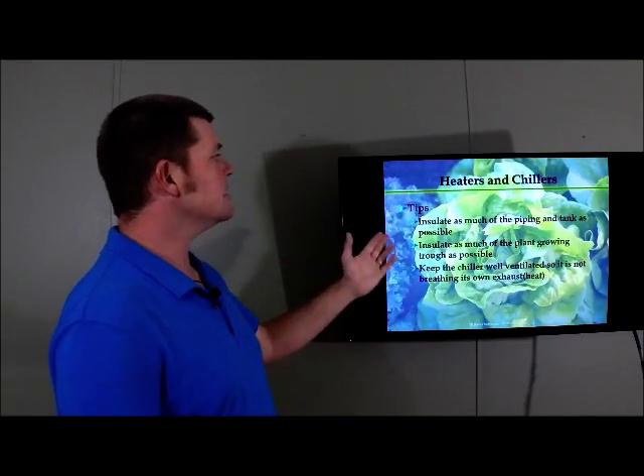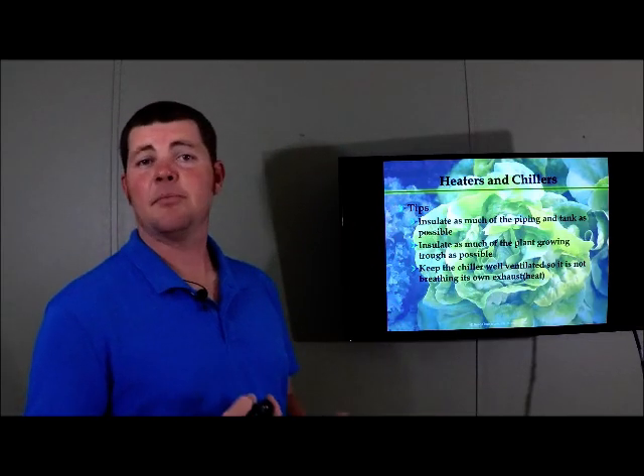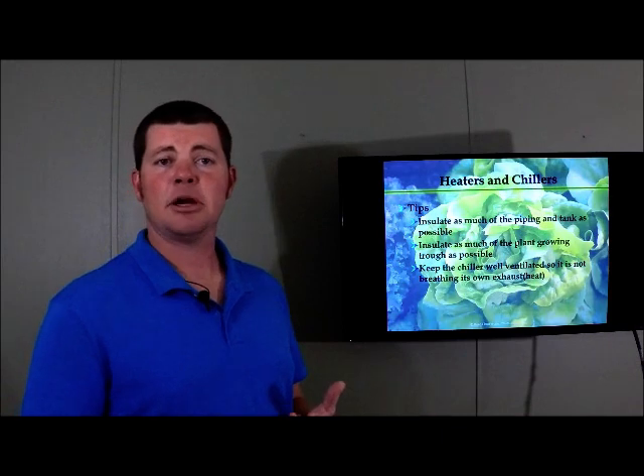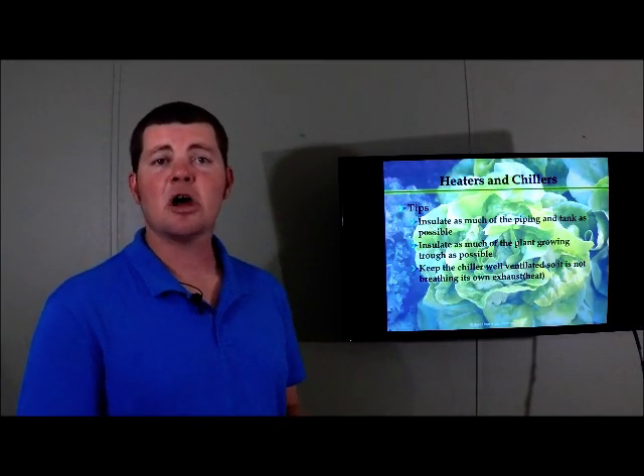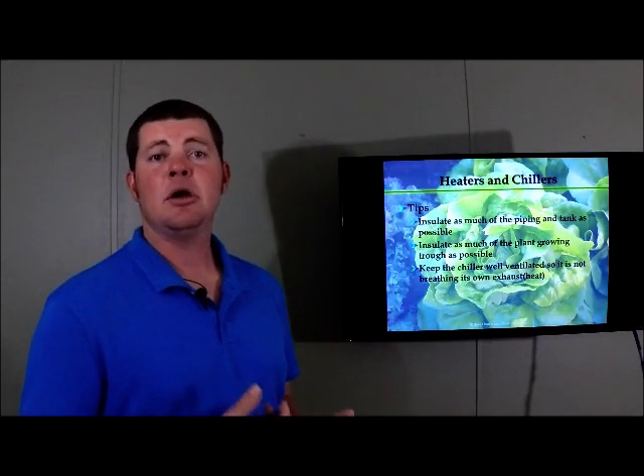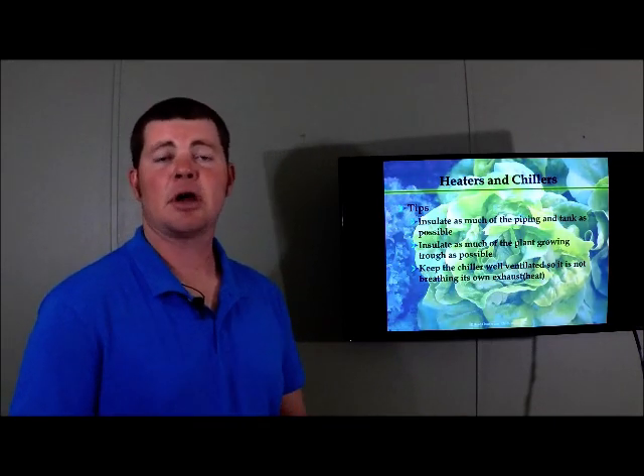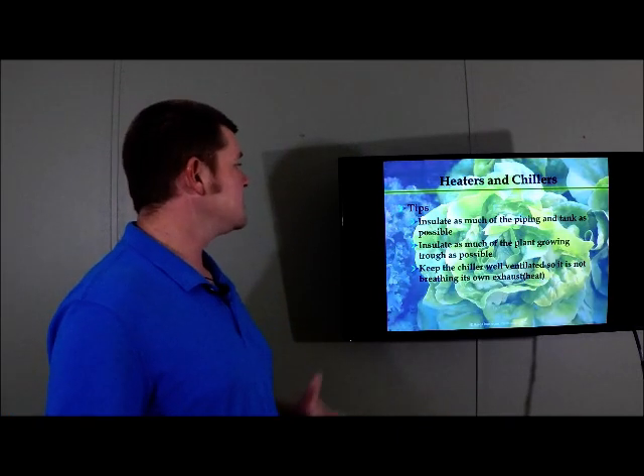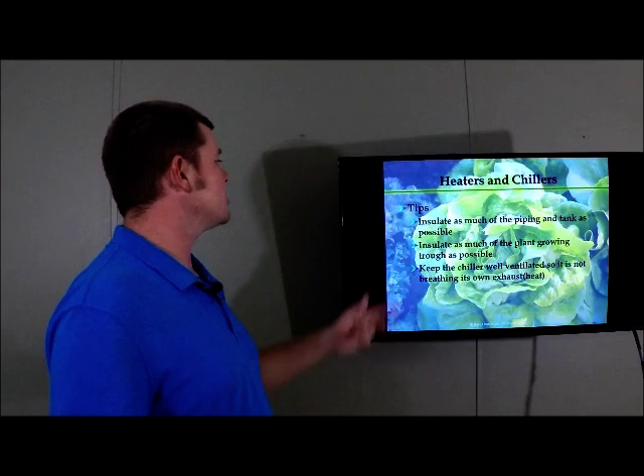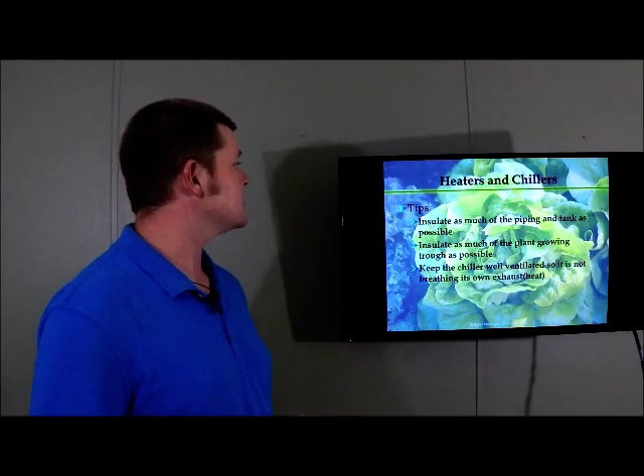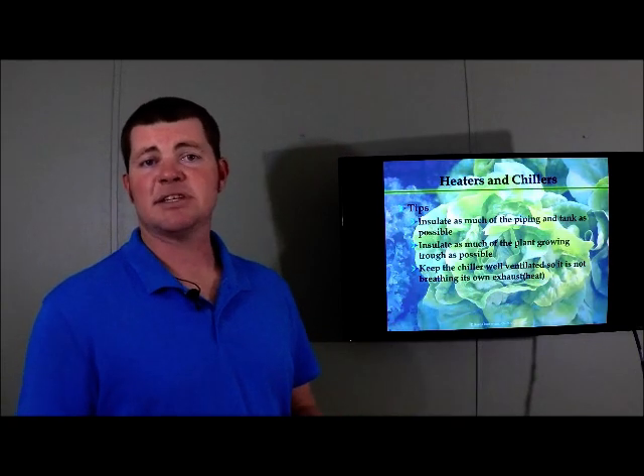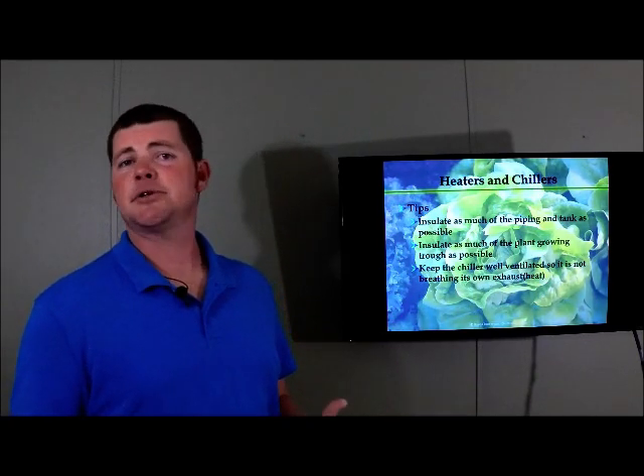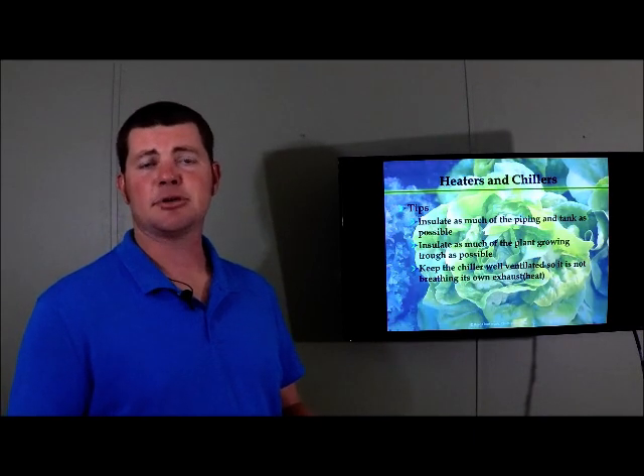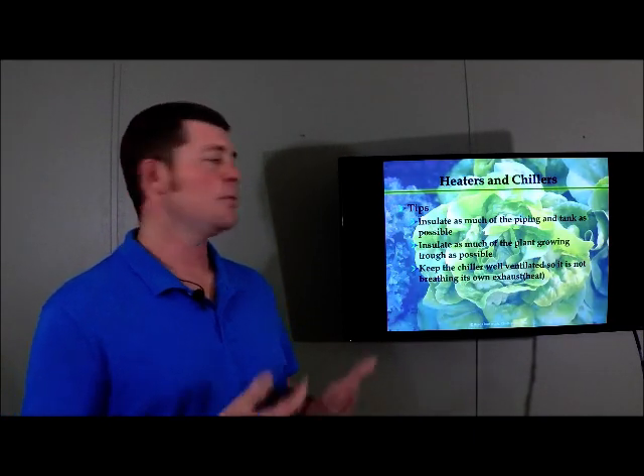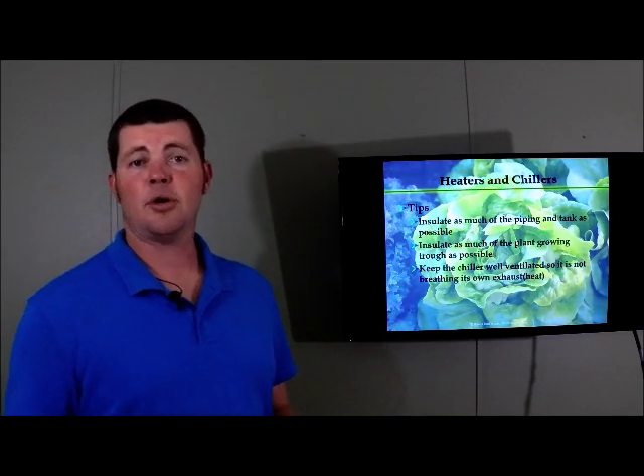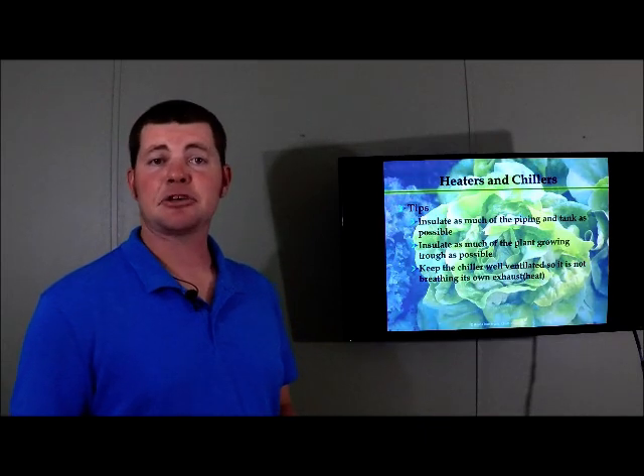So some tips here. Insulate as much of that piping as possible. The more we insulate, which is spending a little bit more money up front, the more it's going to save us long term in energy usage. And I guarantee you, you will spend more money in energy trying to overcome those temperature differences than you will spend on insulation. So insulate as much as possible. Insulate as much of the plant growing trough as possible if, say, your greenhouse is not temperature controlled. If the whole greenhouse is temperature controlled, your trough is going to find the ambient temperature there, the same temperature as the greenhouse. It will come up to that. But if, let's say, you're in an open growing environment, insulate as much as possible if you're actually going to chill that tank.